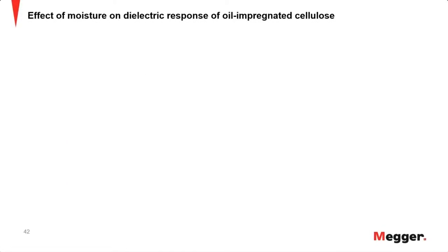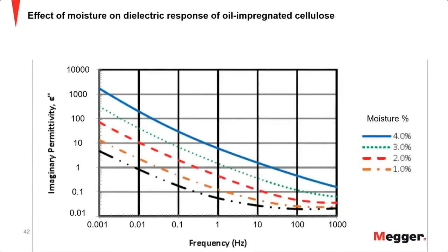And then if we take a look at the effect of just moisture coming from that same standard we were talking about before, here we have a few different curves for different levels of moisture. And we see that the difference between 0, 1, and 2% moisture doesn't have a very big impact on that 60 hertz measurement. But as we go lower down to 1 hertz, we can see that for a bushing or a transformer with 4% moisture, the impact at the 1 hertz measurement is almost 10 times higher than it is at 60 hertz. So certainly when you talk about, say, 1% moisture, that impact is quite significant. It's the sort of magnifying glass that you have on the developing problem with 1 hertz compared to what you would see at 60 hertz.